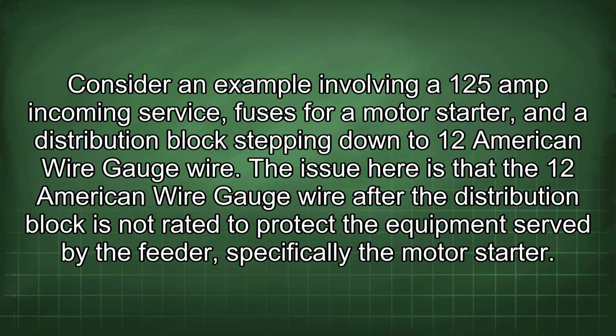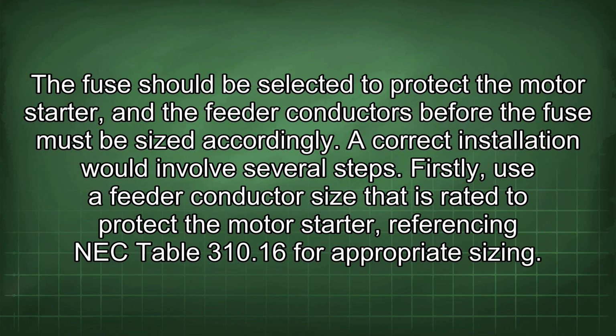Consider an example involving a 125 amp incoming service, fuses for a motor starter, and a distribution block stepping down to 12 American wire gauge wire. The issue here is that the 12 American wire gauge wire after the distribution block is not rated to protect the equipment served by the feeder, specifically the motor starter. The fuse should be selected to protect the motor starter, and the feeder conductors before the fuse must be sized accordingly. A correct installation would involve several steps.